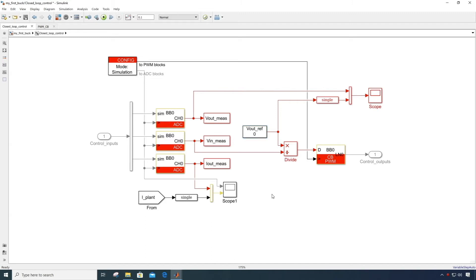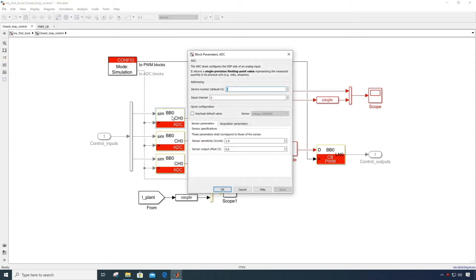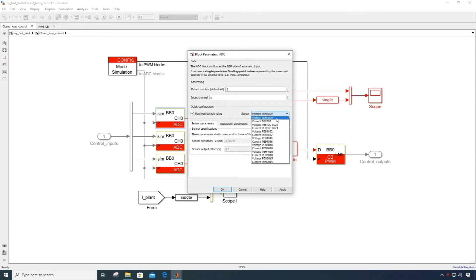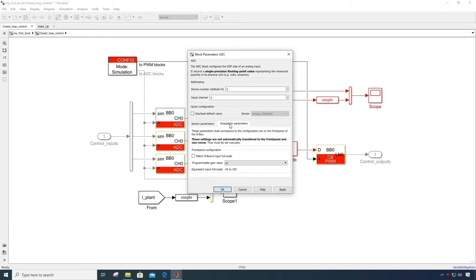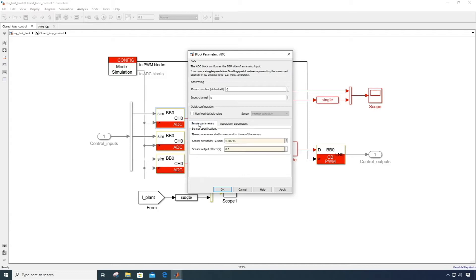I will also configure the ADC blocks to match the parameters of the sensor that we are using and to transfer the parameters that we've just configured on the BBOX front panel. For instance, on channel 0, we can load the predefined parameters of the external voltage sensor and specify the scaling gain of 8 times. Then we do the same for the channels 1 and 2.